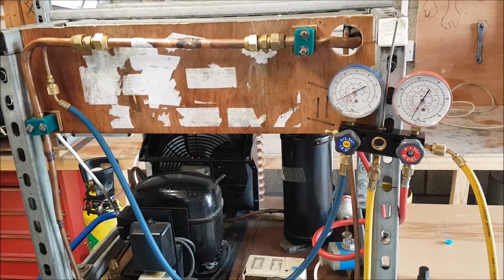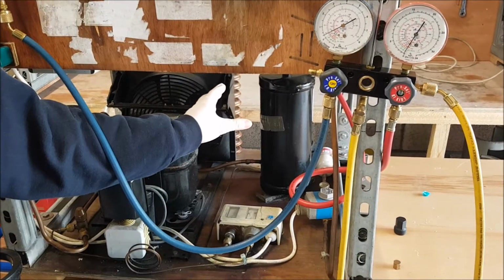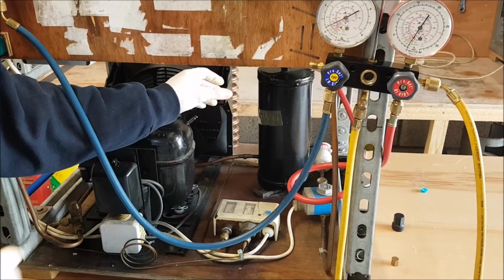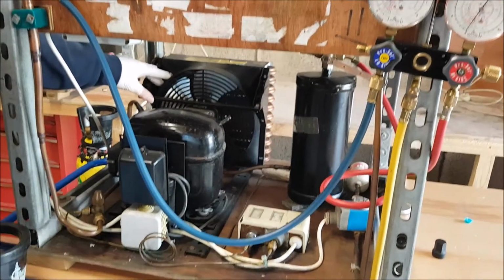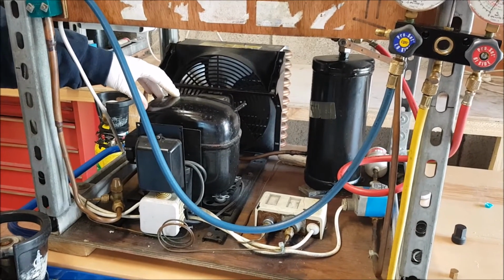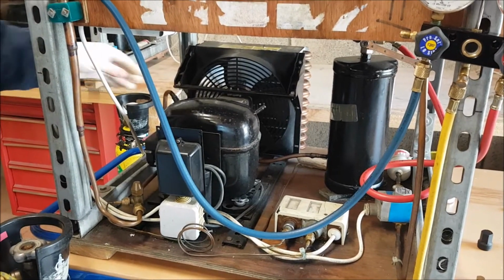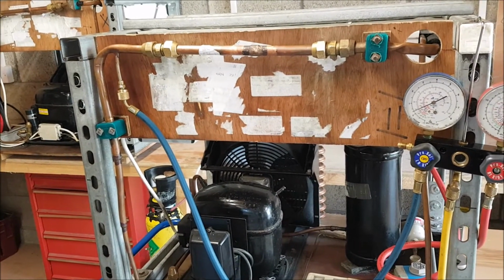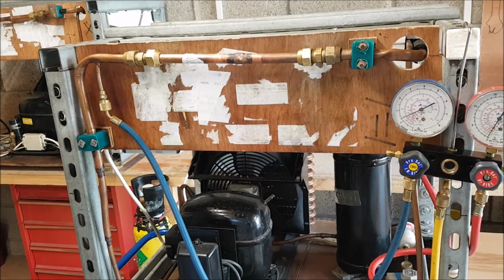But if we're in a scenario whereby we have to change this high side capillary, for example, then pumping down will not help us prevent refrigerant loss as soon as we disconnect this capillary line. Therefore, we must recover all the refrigerant. If we needed to carry out repairs on the condenser, again, we need to recover refrigerant. In this particular scenario, because there's no isolating valve on the discharge side of the compressor, if we needed to remove or replace this compressor, again, recovery is required. So there are definitive times when we must recover refrigerant to carry out repairs, and there are occasions when we can carry out a pump down sequence to carry out repairs.